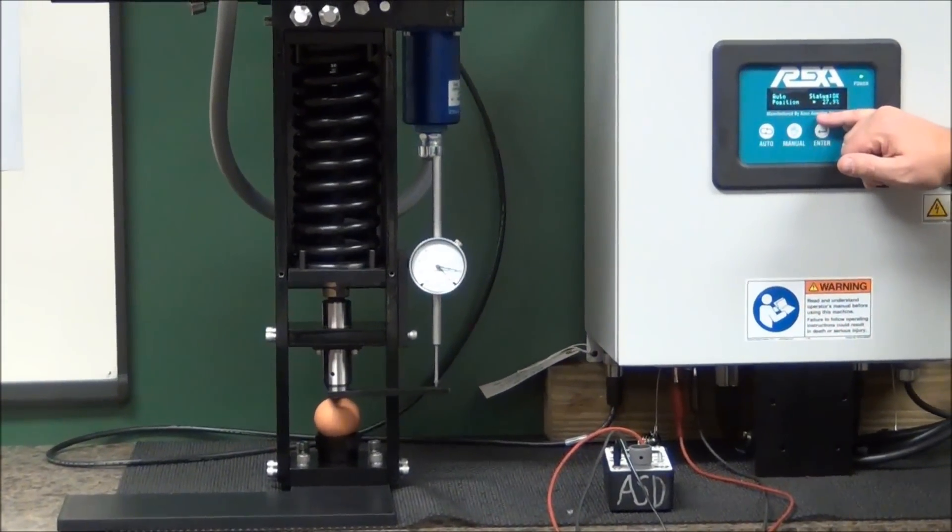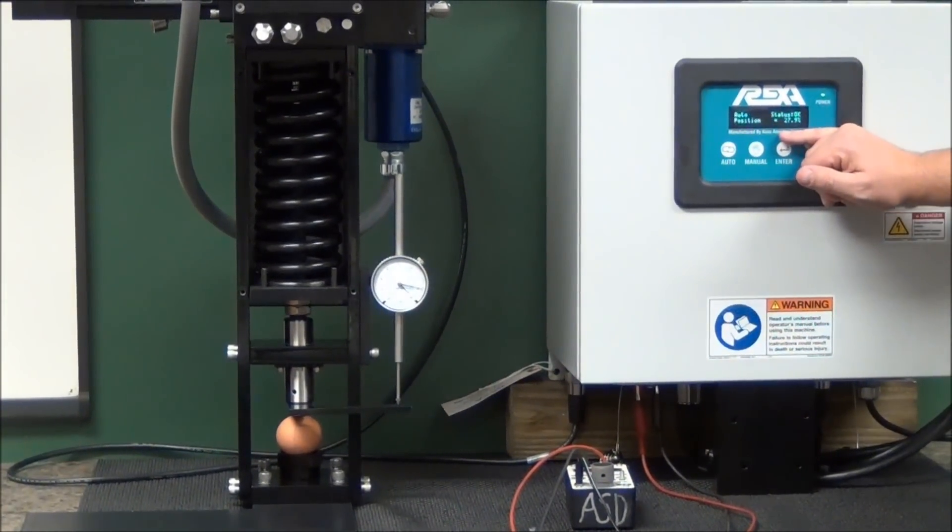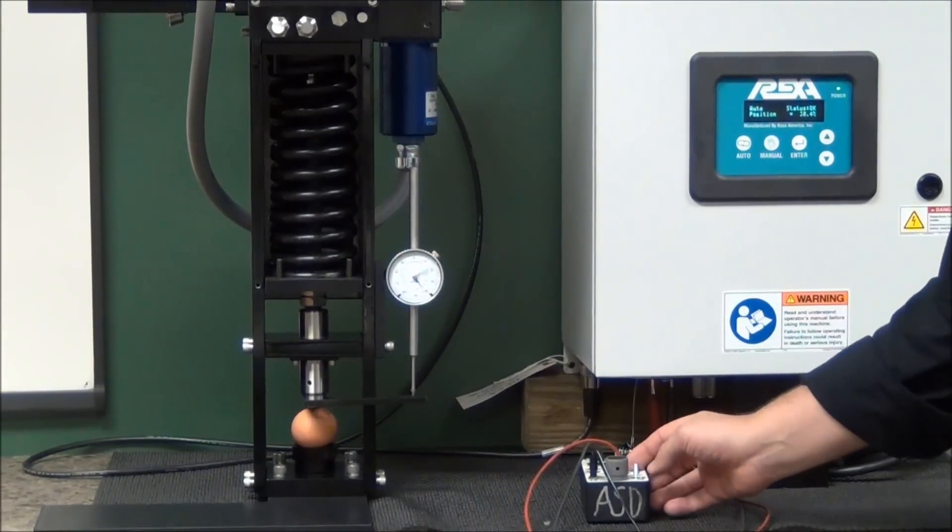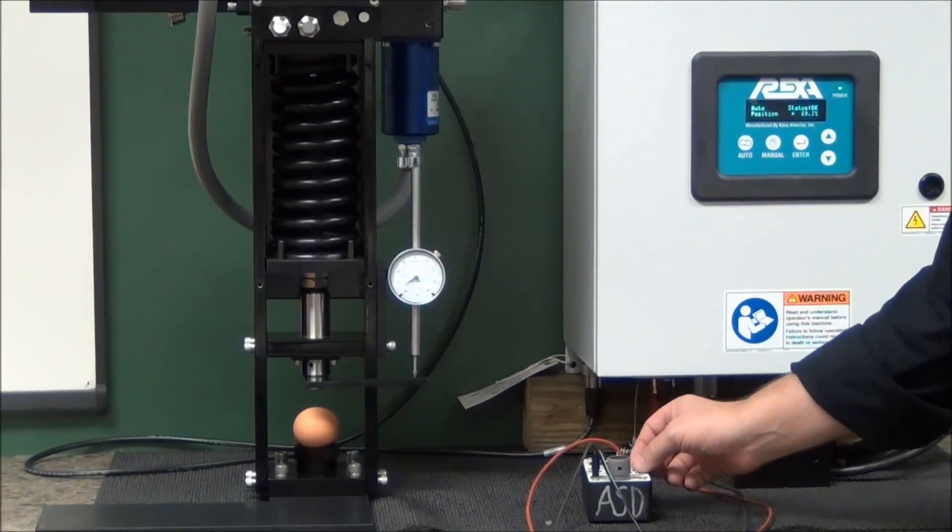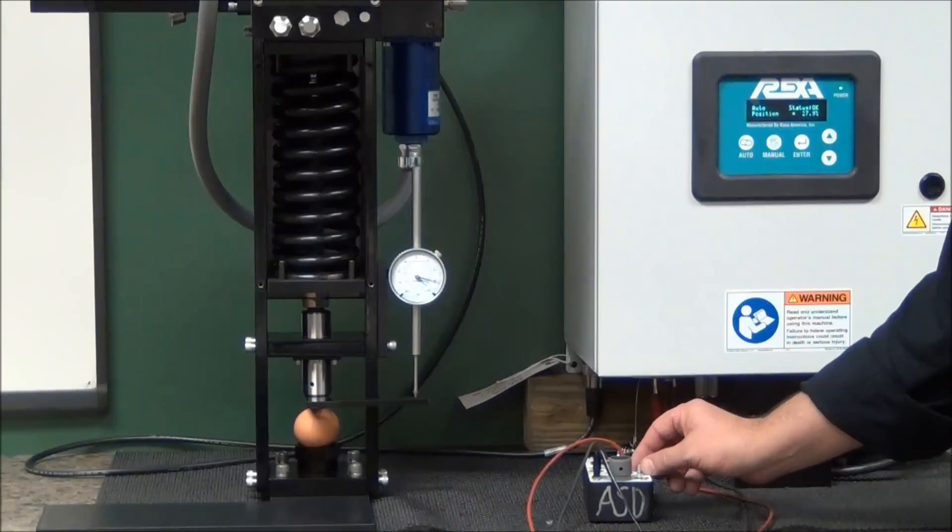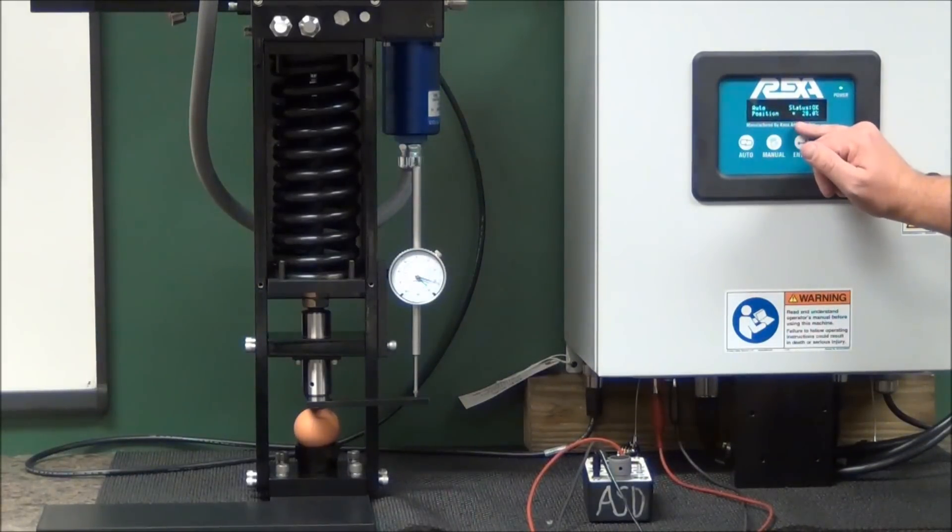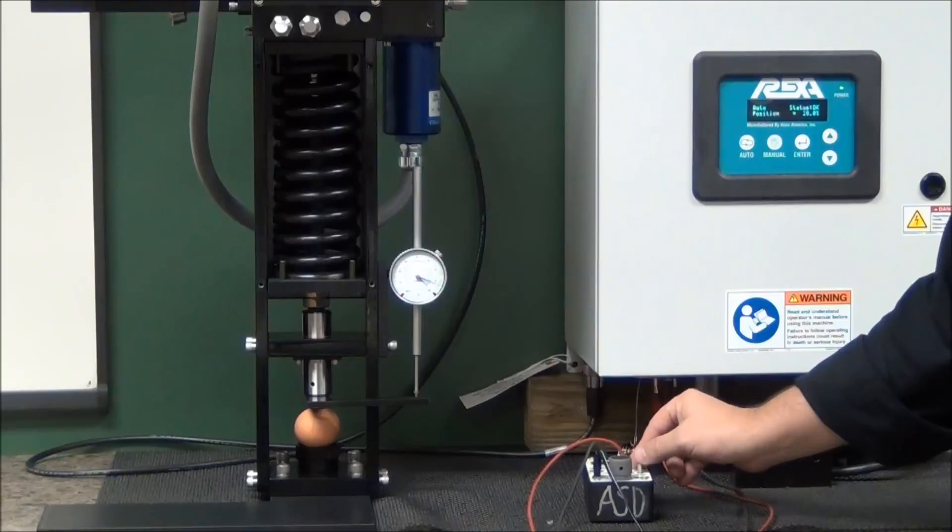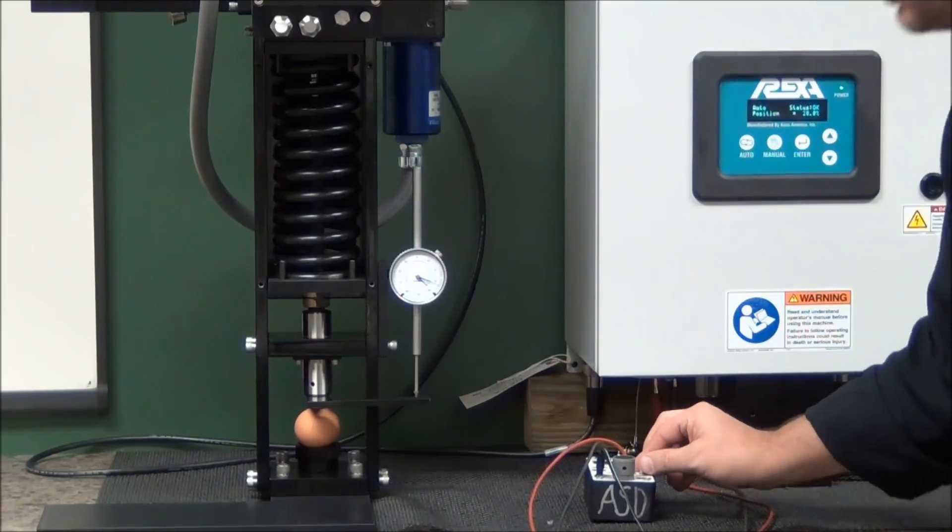Now I'm going to run it up to 100% and bring it back down to 27%. So I've instantly brought my signal from 100% to 28%. The egg did not break. It did not overshoot.